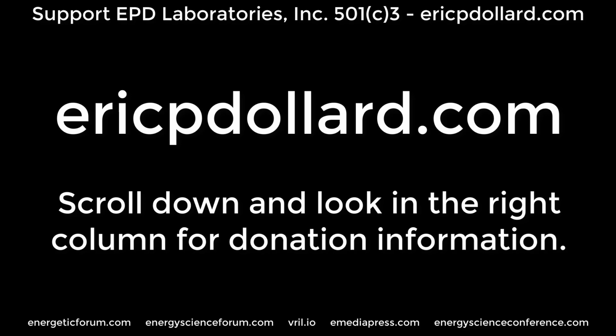So let's say I had money to build a laboratory. There'd be a lot of Bell System equipment running off DC, with typical magnetic amplifier regulated rectifiers converting AC to DC to power the equipment and float the batteries. But I'd also want to go from DC to AC, so that if the public utility system fails, I wouldn't need roaring generators. Because of my way of thinking, and the severe electromagnetic compatibility problem I have here — very low-level signals running around everywhere and radio equipment operating — I would not use solid-state square-wave, transient-generating inverters or anything like that.